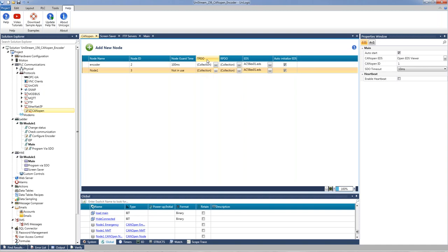Now, a quick explanation of what's going on here. With CANopen, there are three major message types that it sends. It has NMT commands, or network management commands, SDO commands, service data object commands, and PDO, process data object commands. So NMT are system type things like turning the device on, turning the device off, the operational states of the device. The SDOs are like the configuration values and different settings on that device. The PDOs are really the process values. They're the information that we're after.